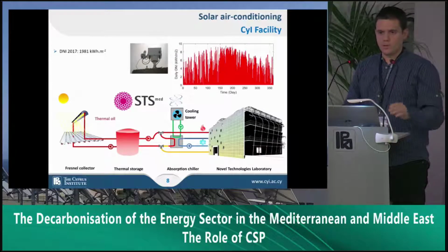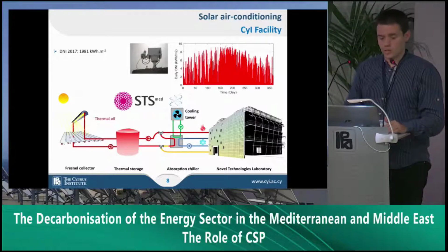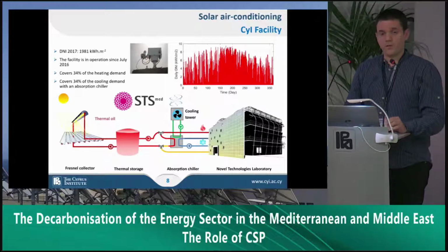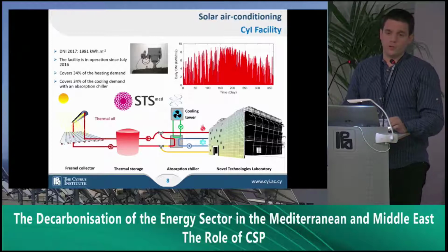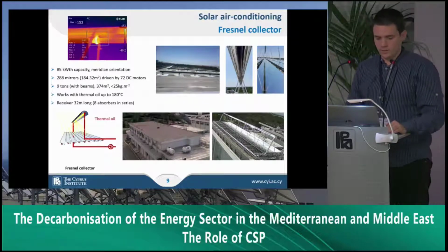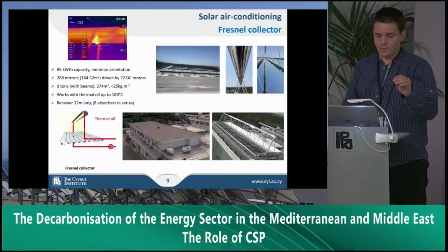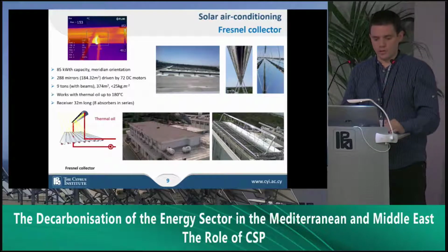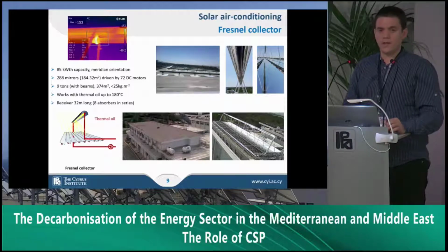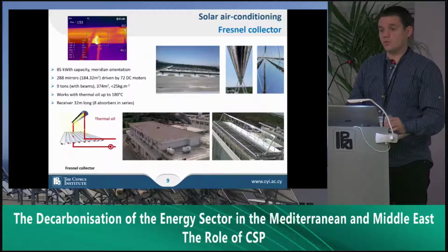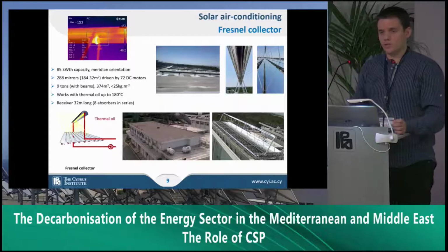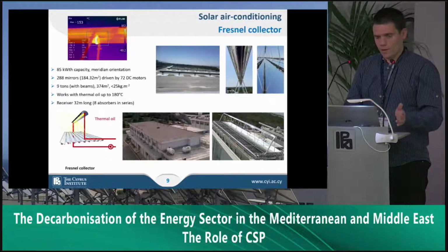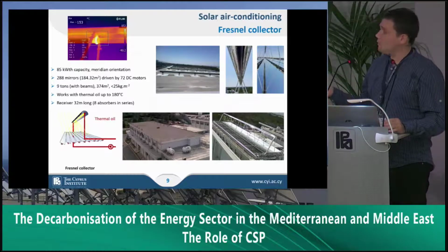The DNI registered with our pyrheliometer here installed on the top of the roof was almost 2,000 kilowatt hour per square meter. The facility is in operation since 2016, and it covers up to 34% of the cooling and heating needs of this building here. The collector itself has a thermal peak capacity of 85 kilowatts. It has a north-south orientation, 288 mirrors driven by 72 DC motors, 9 tons, and this represents less than 25 kilograms per square meter. So even on an old building, we could integrate easily this facility, okay, with the help of some beams that you can see here.